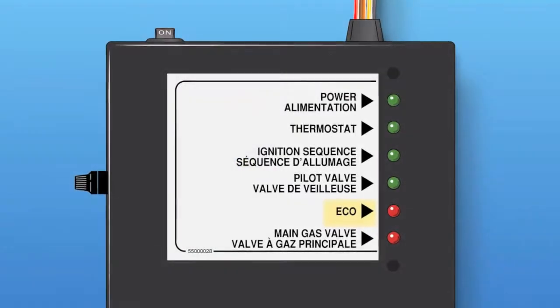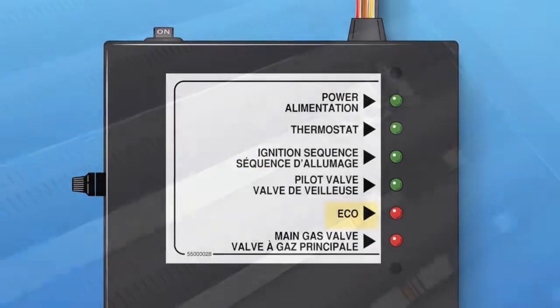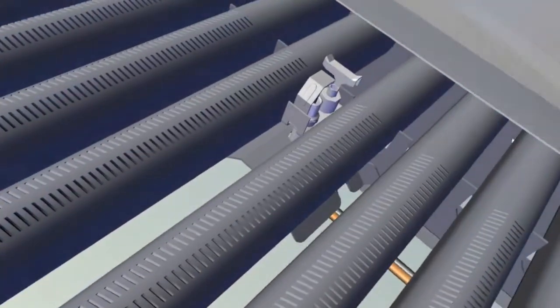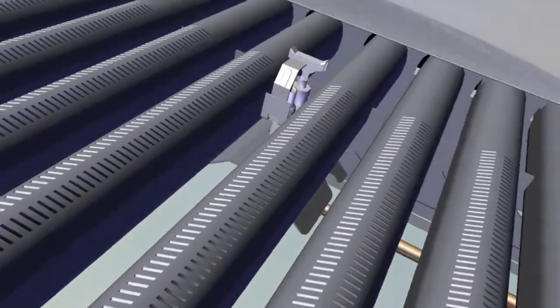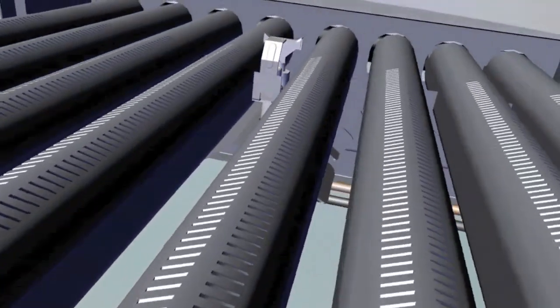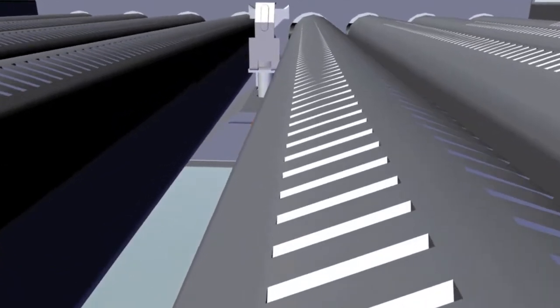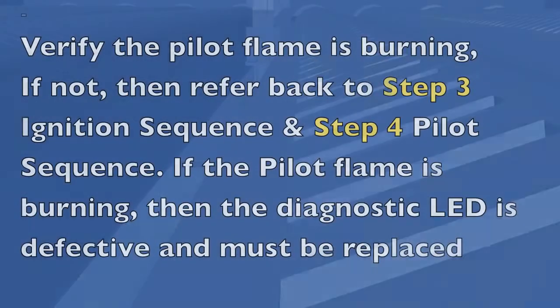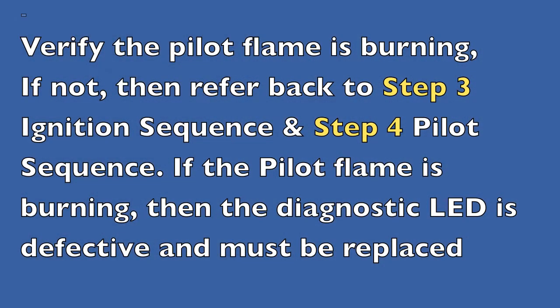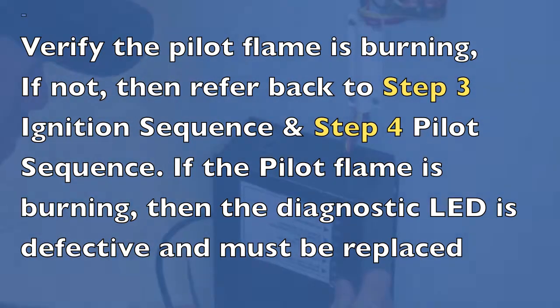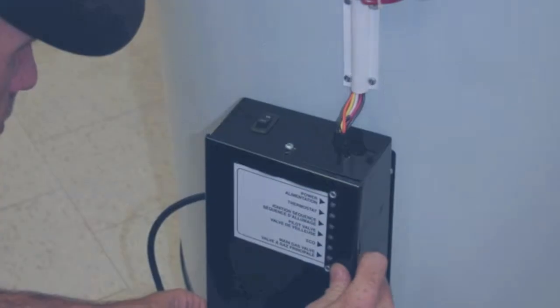If the ECO LED is still red, then verify the pilot flame is burning. If not, then refer back to Step 3, Ignition Sequence, and Step 4, Pilot Sequence. If the pilot flame is burning, then the diagnostic LED is defective and must be replaced.